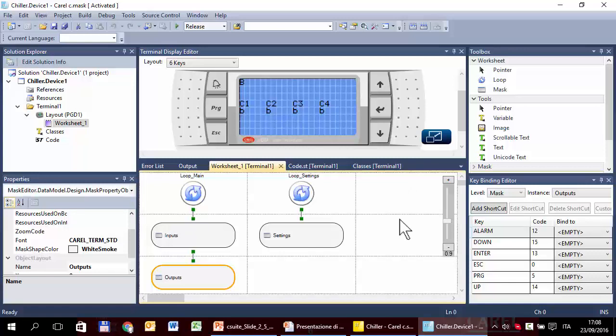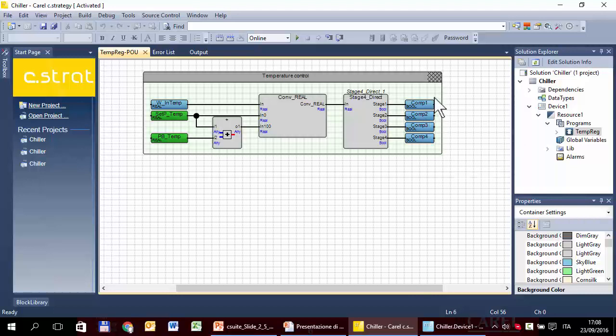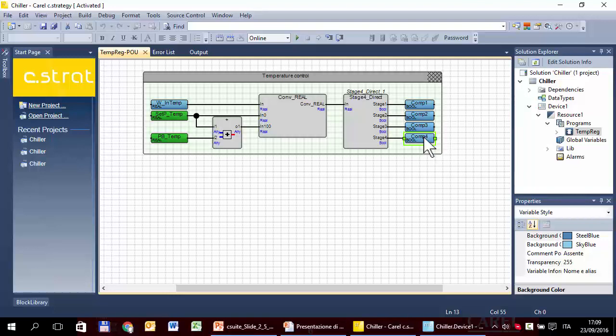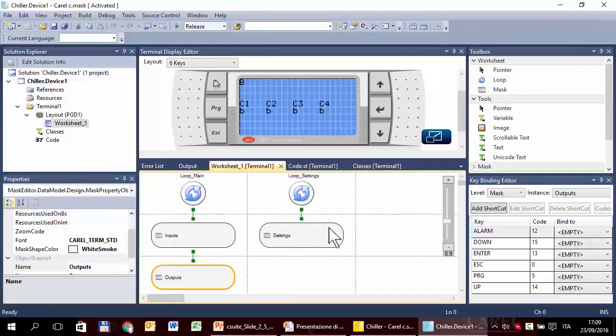Then we have to enable the compressors. Enabling means two things. The first is to enable the mask — that is, let the final user enter a mask, for example the mask showing the status of compressor four, only if there are at least four compressors used. The second is to enable the compressor relay, for example switching on the compressor not only according to the temperature, but also according to the enable state of the compressor. Let's start.